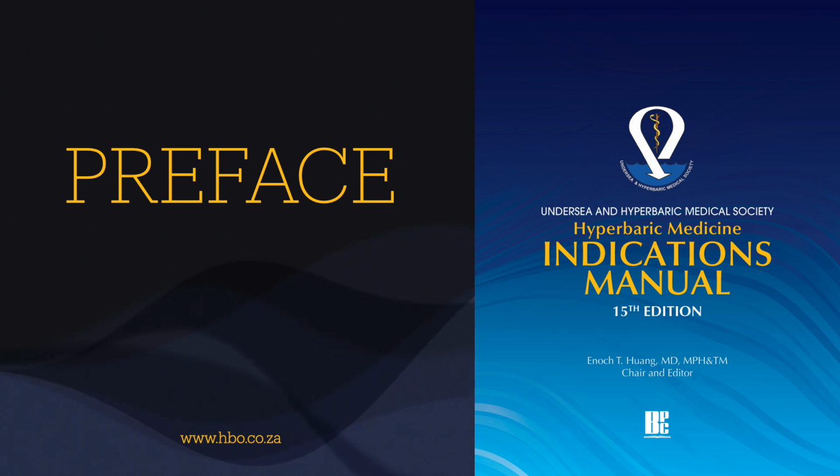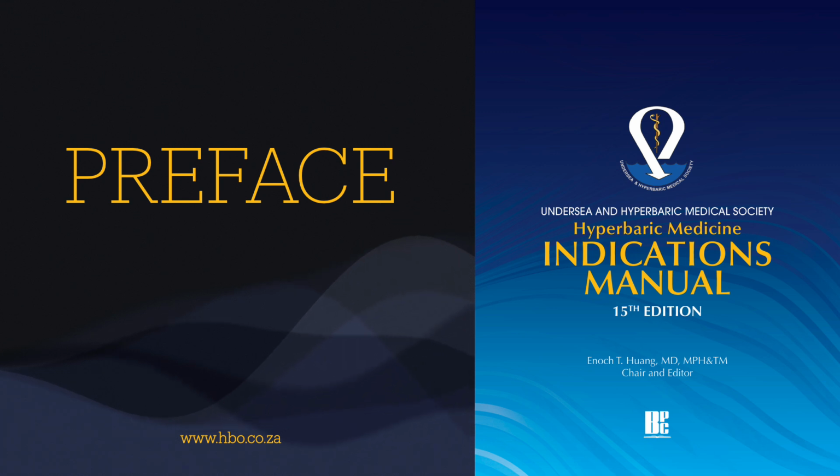Okay, what about the pressure itself? The manual states the treatment must be administered at a pressure of not less than 2.0 atmospheres absolute. 2.0 ATA minimum. Right. And the manual gives the conversion, 202.65 kilopascals. This pressure threshold is fundamental to achieving the therapeutic effects, particularly getting significantly more oxygen dissolved in the plasma.